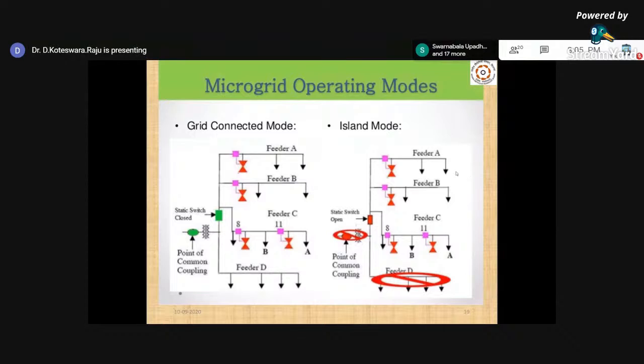If something happens and the switch is open, this feeder is not at all connected to the utility grid. So feeder D is not supplied by the microgrid anymore. Only the microgrid supplies its own feeders and own loads within clearly defined boundaries, meaning feeder A, B, and C will be served from the microgrid. This mode is called island mode.